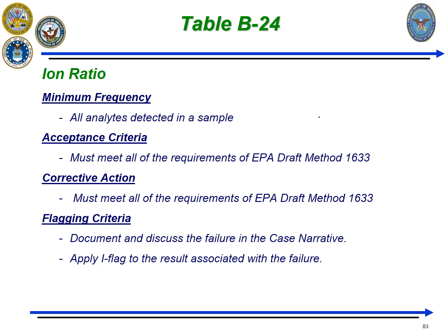We also specified further the flagging criteria that would be required. The method itself required data to be flagged, but it did not provide any information on what flag data qualifier needed to be used. In accordance with the typical DoD QSM requirements, we are requiring any failure to be discussed in the case narrative as well as being flagged. So we had made that clarification as well.